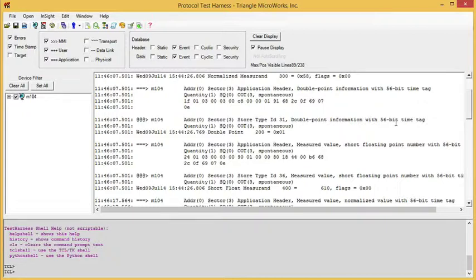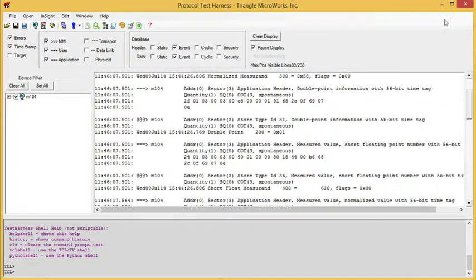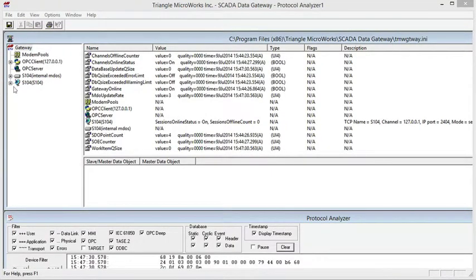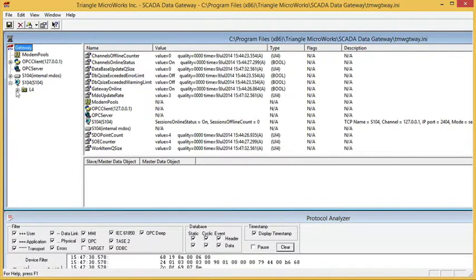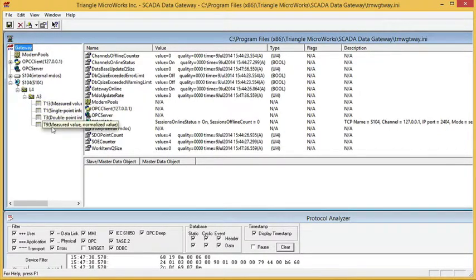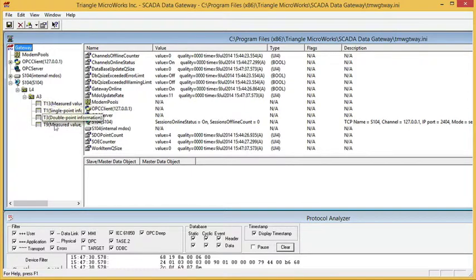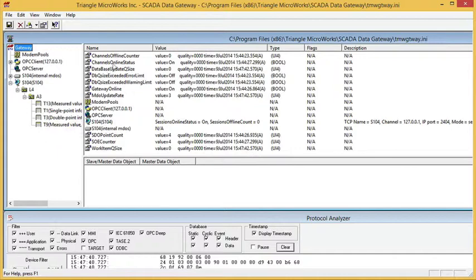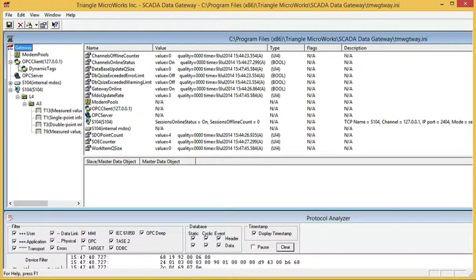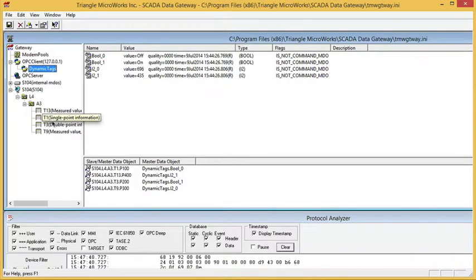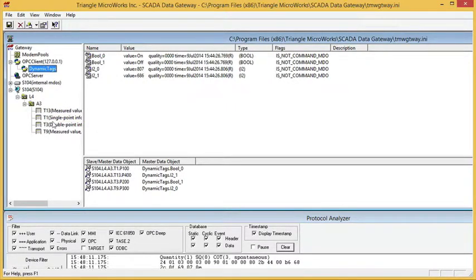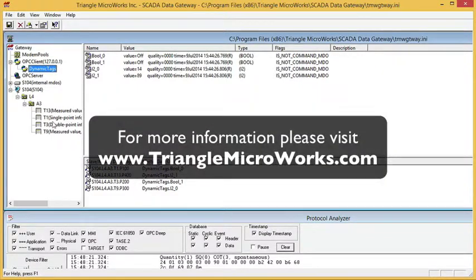So in summary, when you configure your SCADA data gateway, you use the base type, even though it doesn't show a time tag. You create points in a slave component by mapping. You can simply drag and drop points from a master component to the slave. In this case, we dragged them from the OPC client to the appropriate data type. And then if you want to send time tags on points that do not send time tags by default, you need to modify the INI file and set the time tag type to be sent.